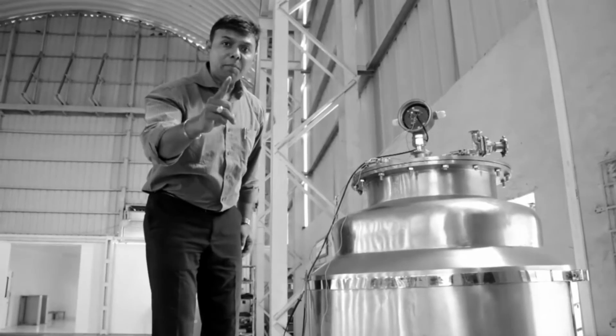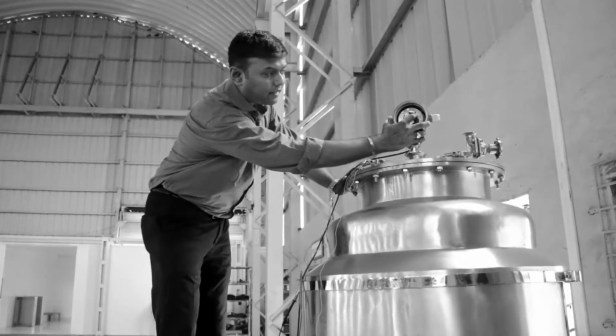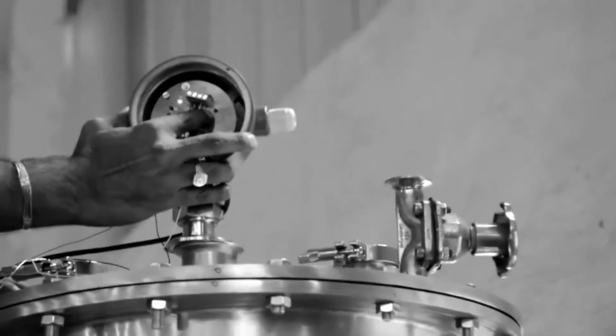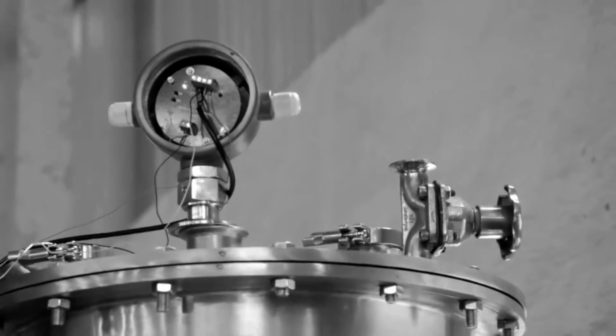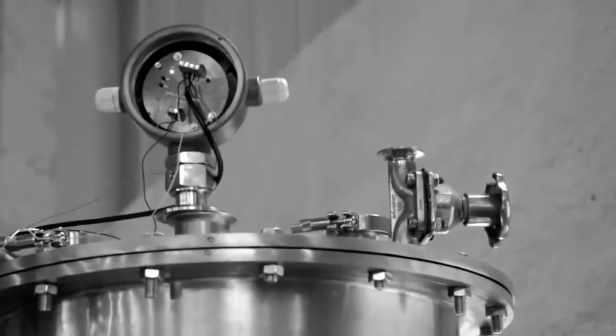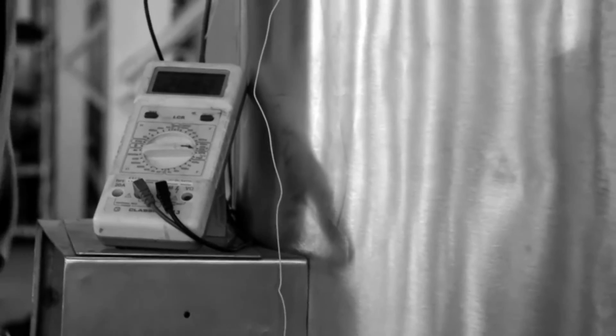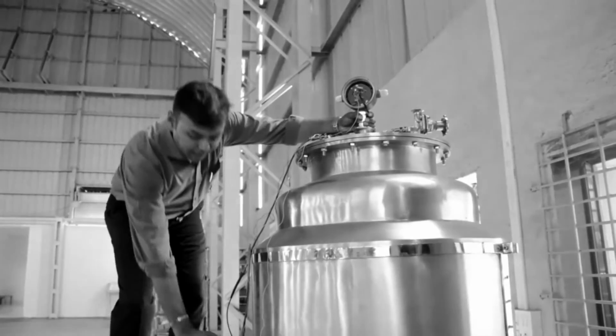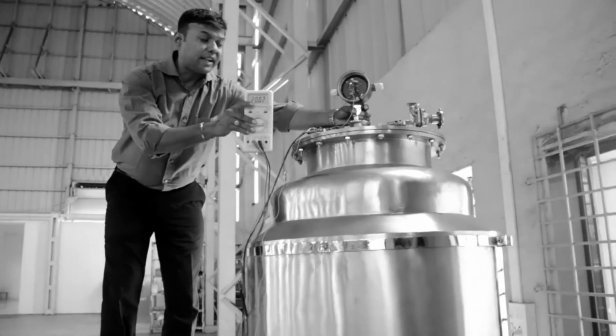I have pressed the minimum button once more. You can see that the calibration LED has gone off, which means that we have come out of the calibration process and the calibration is complete. You can check this. Now when I am lifting up the transmitter slowly, you can see that this reading is gradually decreasing.